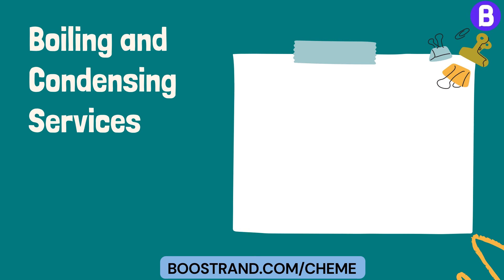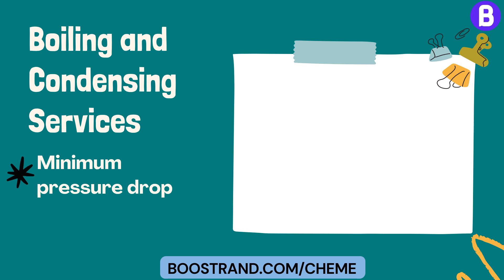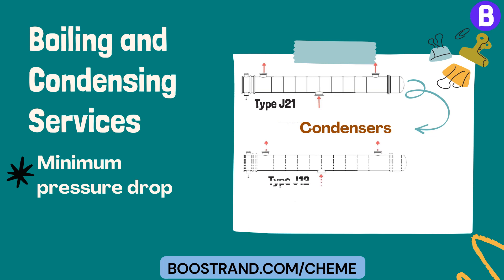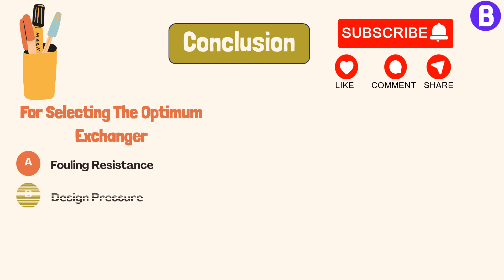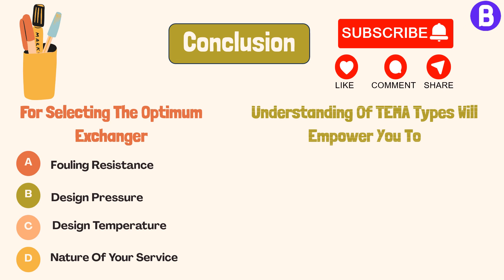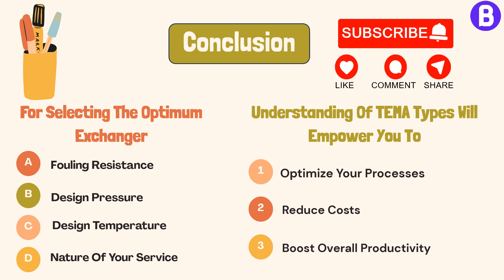We can also use the divided flow shell type — in other words J type — if we want the minimum pressure drop. Distributing the inlet flow for condensers, or the outlet flow for reboilers, can reduce the pressure drop significantly. That's why it's common to use a J21 shell type for condensers and J12 type for thermosyphon reboilers, with the front and rear head type selected based on cleaning requirements. Selecting the optimum exchanger TEMA type is an essential aspect of ensuring efficient heat transfer in your industrial processes. By considering factors like fouling resistance, design pressure and temperature, and the nature of your service, a thorough understanding of TEMA types will empower you to optimize your processes, reduce costs, and boost overall productivity.